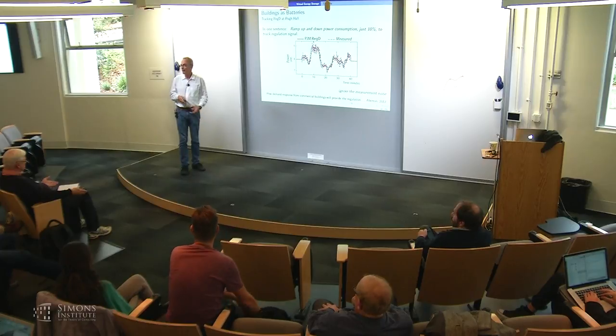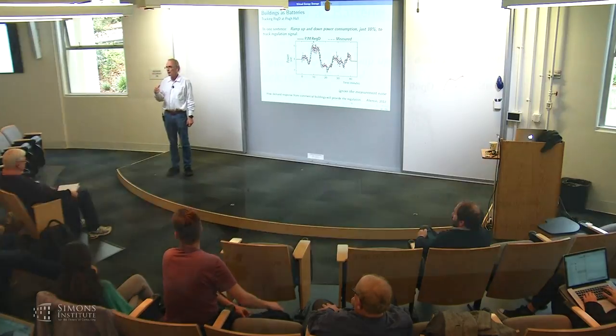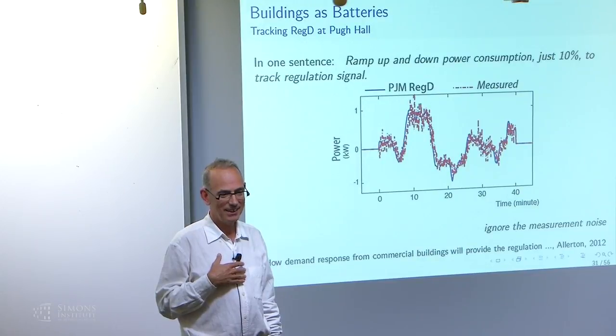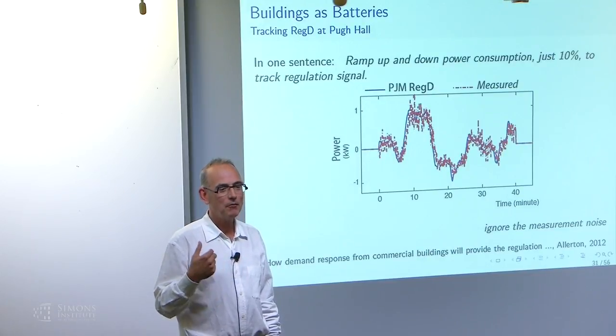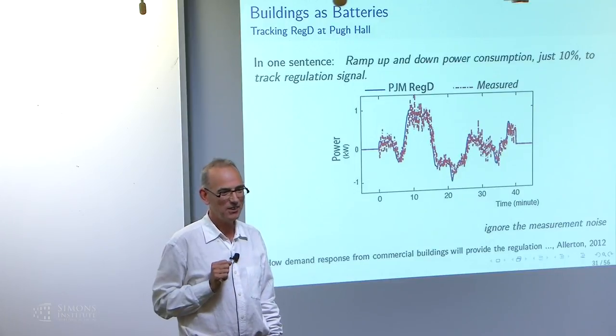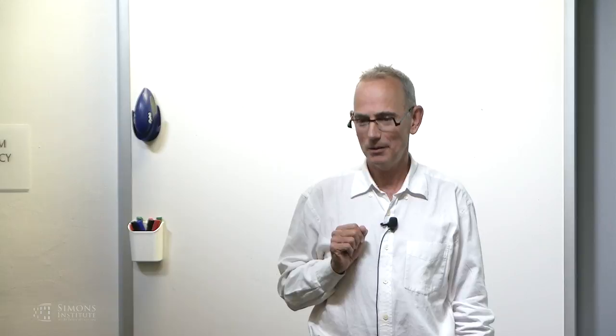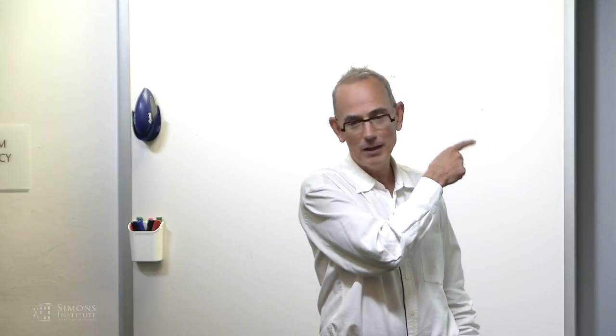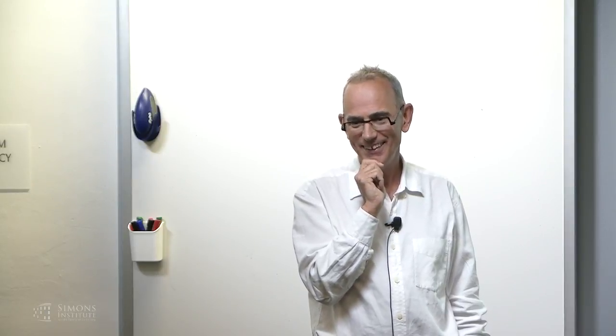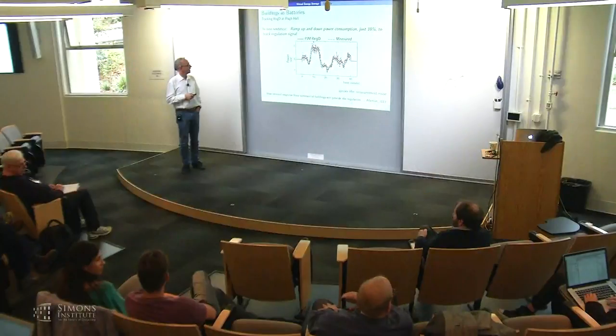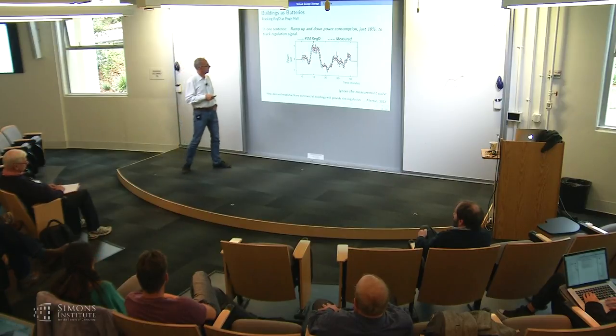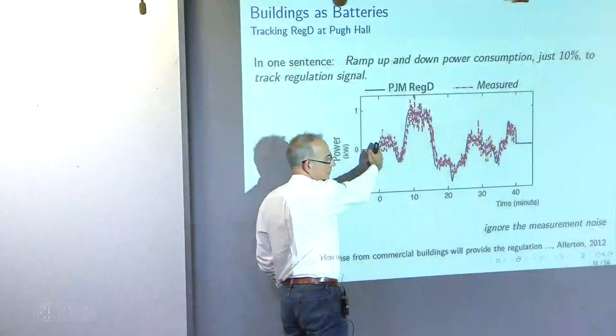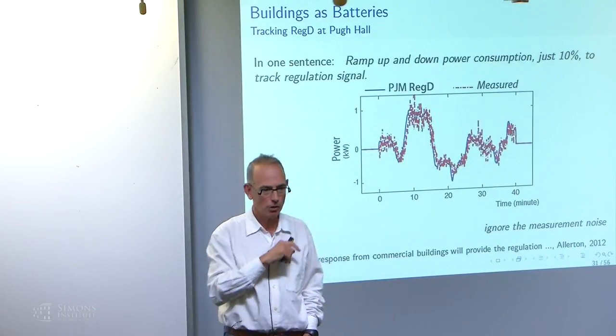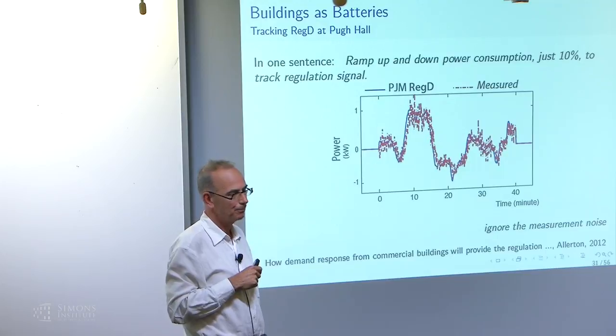Yes, it can, in the sense that it's deviating, increasing its speed 10% or decreasing 10%. Batteries can't do that, but the zero line actually represents consumption of some kilowatts. It doesn't matter though, because from what the balancing authority wants, they want deviation. They don't care at all about the power consumption, they care about deviation. So this is better than any battery could ever do, the service is much better than any battery would provide. It's deviation that we care about. Is the zero a reference, or is it actually zero power? Zero is a reference, we subtracted off the power consumption, the constant power it would have been at that time.